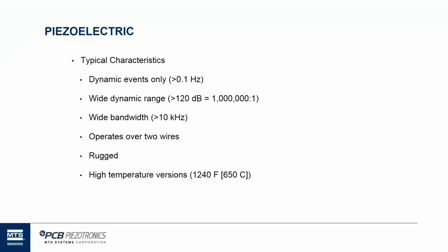That piezoelectric crystal is very stiff. The mechanical ground is very stiff. And finally, the tungsten inertial mass is very stiff and not brittle at all. They can withstand shock events without incurring damage to the sensor.